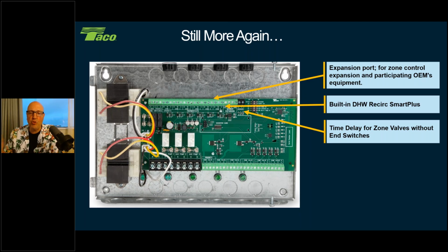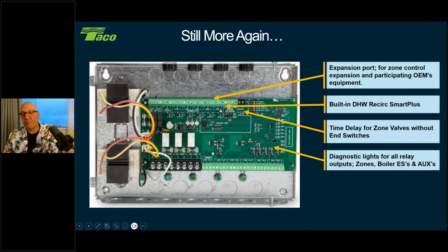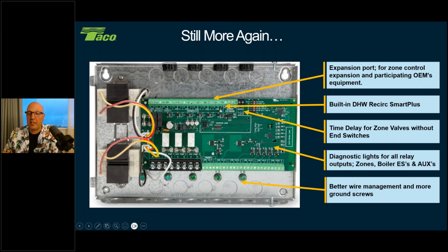And if you had to use one of these on a Dash 4 control, you had to put a jumper across your 3 and 4 terminal in order to fake the end switch, because we never got the signal back from the unit itself. Well, now we have, and those actuators on a radiant manifold take a little while to open up, and we have a default of 1 minute for that valve to open. Again, we got our diagnostic lights on there and the wiring like we talked about before.